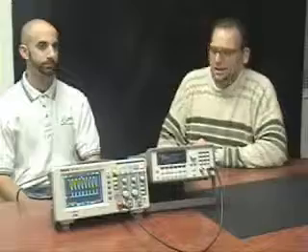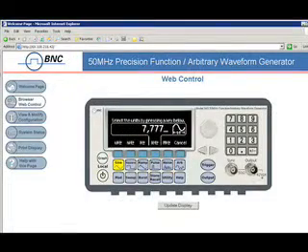We have an ethernet connector on the back panel and we can put this unit on your network, and then multiple users can pull up the front panel from their desktop and control the unit simultaneously. This is ideal for teaching — that's what we basically developed the software for, and it kind of spilled over to clean rooms and laboratories that might be testing.